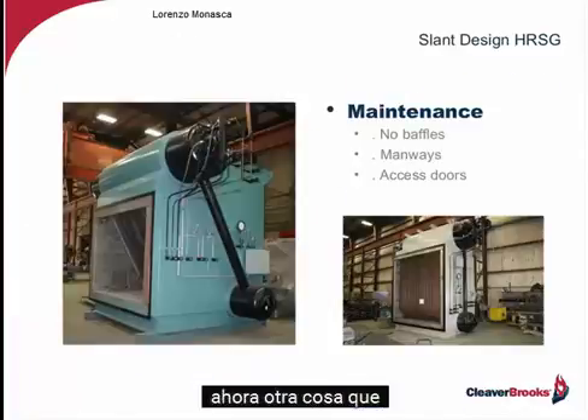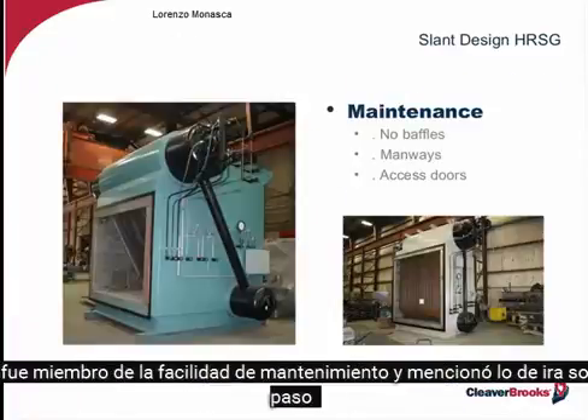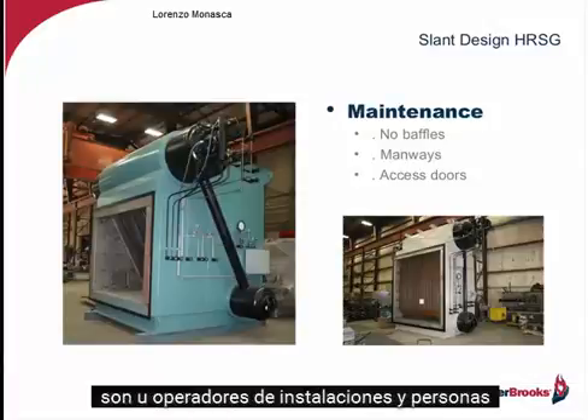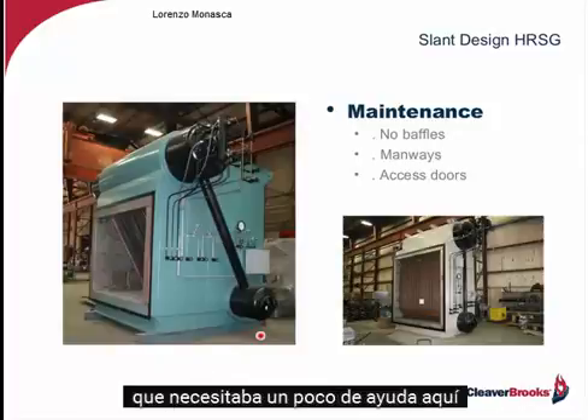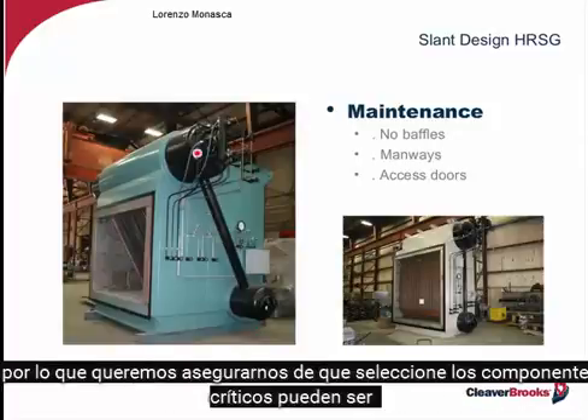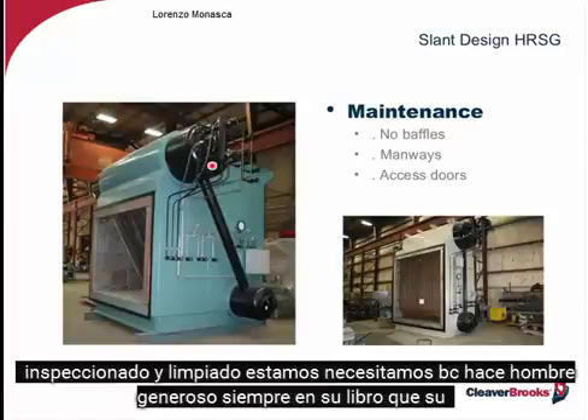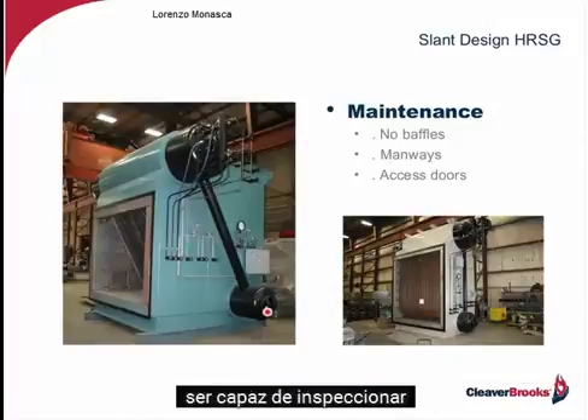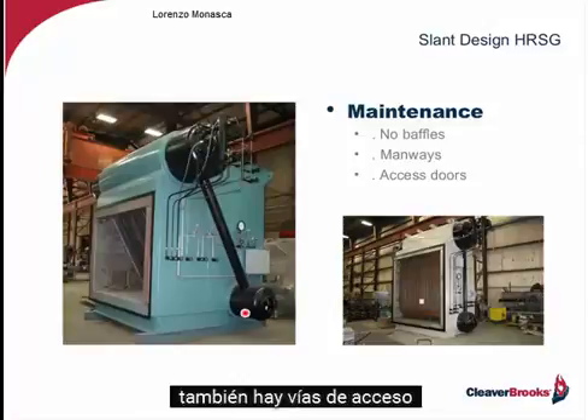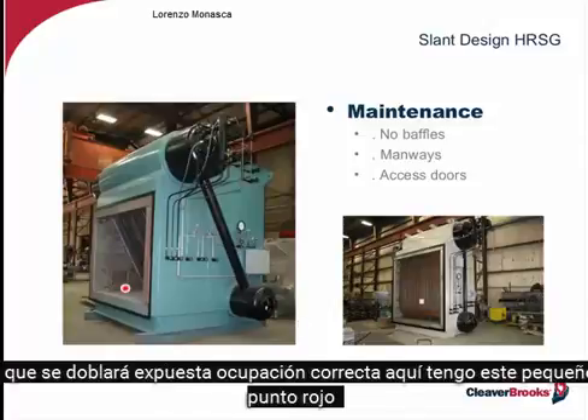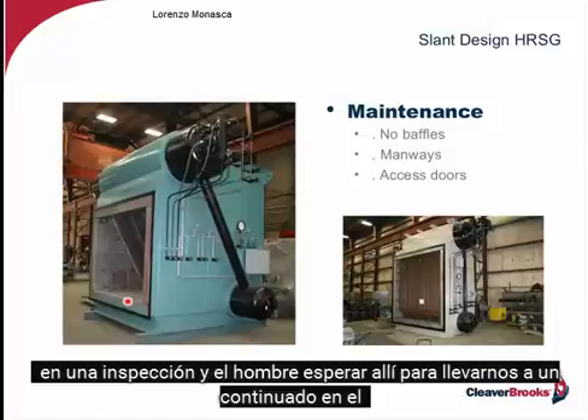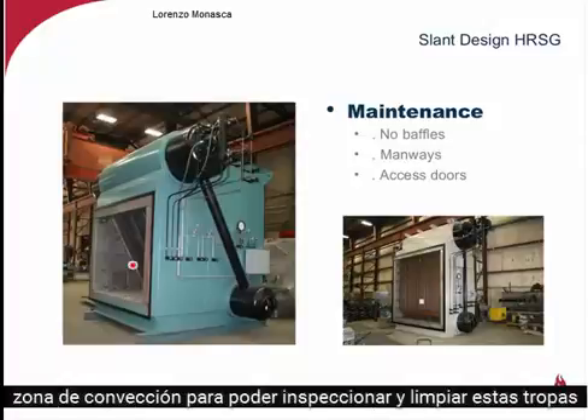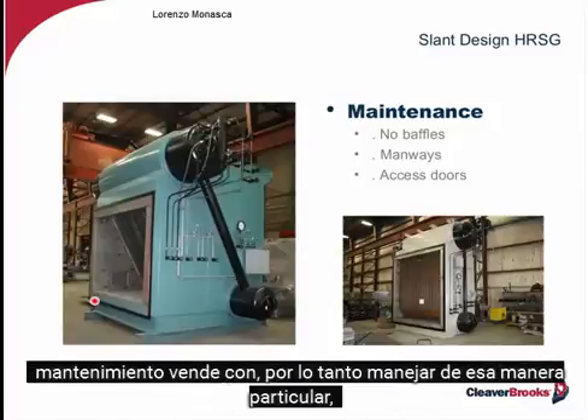Now, one other thing that the spec called for was ease of maintenance. Remember I mentioned that thing about our staff, our boiler operators and facility people. They needed some help here. So we want to make sure that some of the critical components can be inspected and cleaned where need be. So you've got generous manways in both your upper drum and your lower drum to be able to inspect and/or repair. You also have access ways that will then expose, you can see one right here where I've got this little red dot, that's an inspection and manway there to get us into the convection zone to be able to inspect and clean these tubes. So maintenance was therefore handled in that particular way.